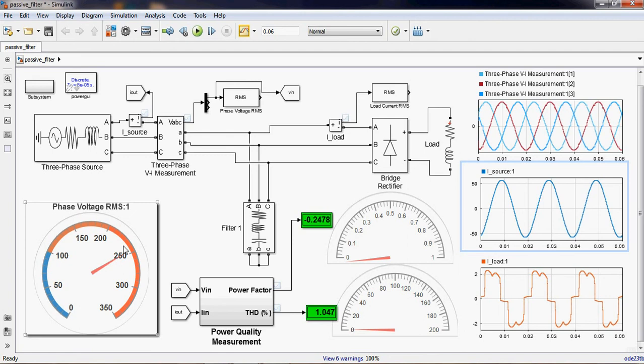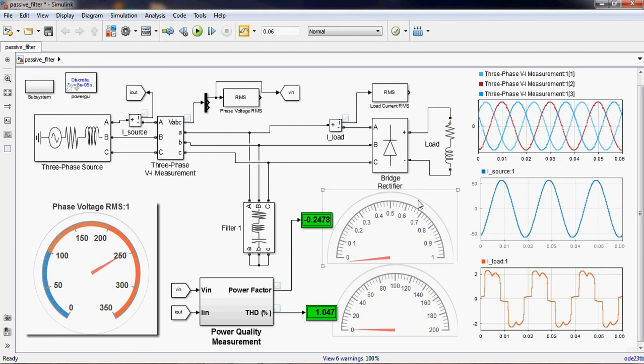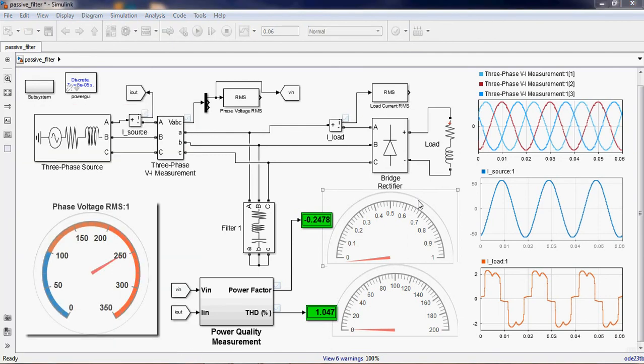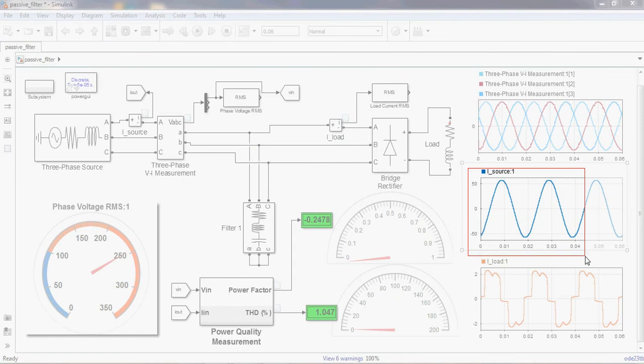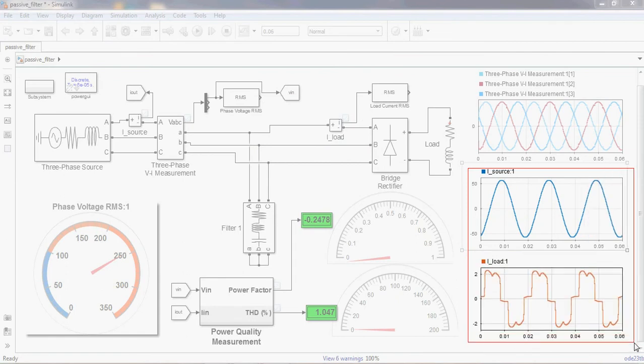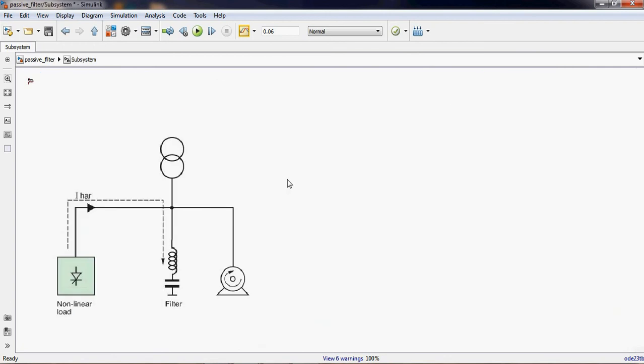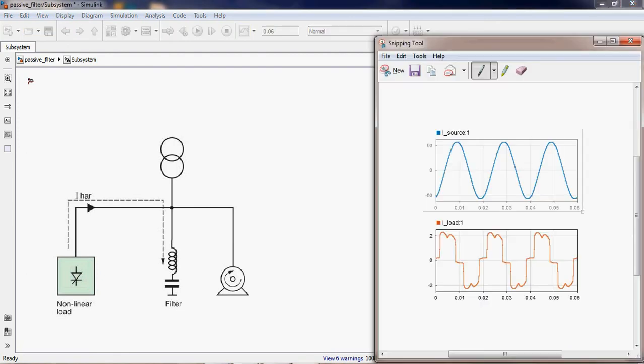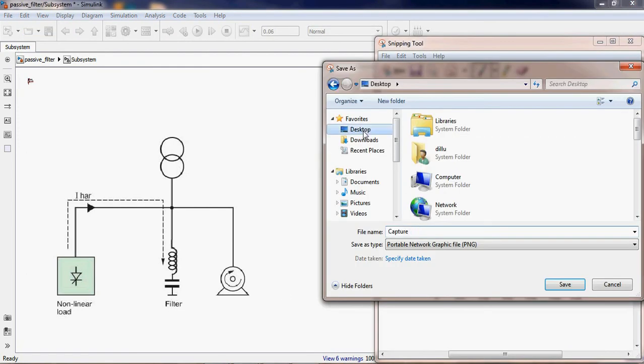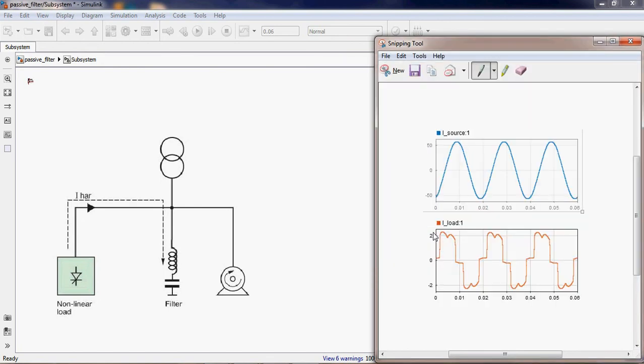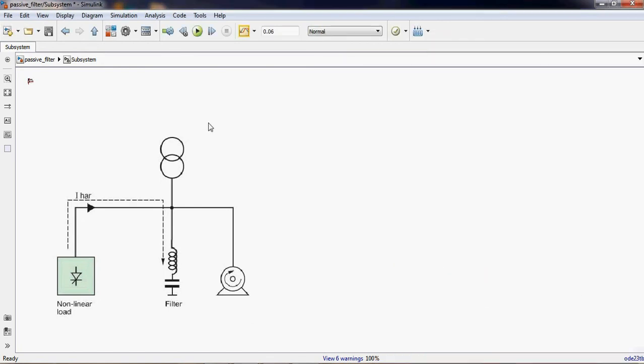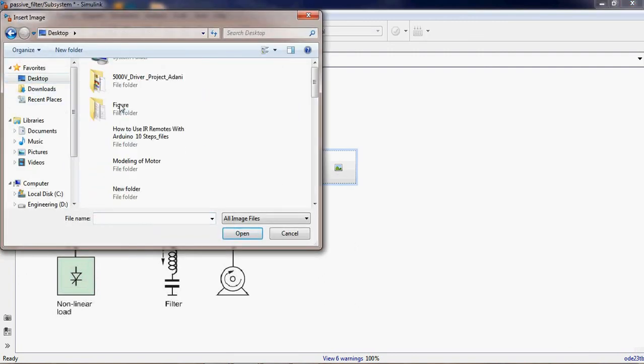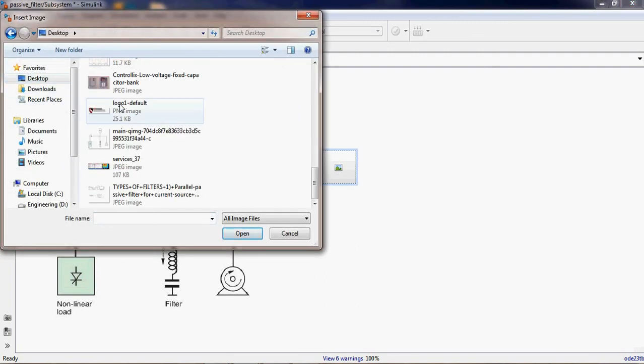You can see the power factor has also improved and THD is reduced from 24 or 26 percentage to one percentage in relief, and the phase voltage is maintained as we set it up. For the reference we will take the snapshot now. We have the comparison here, you can see.